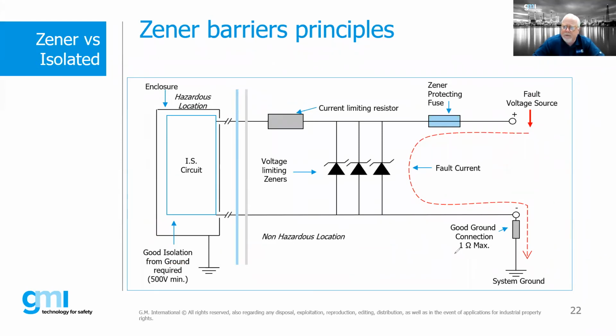But notice this: 1 ohm max, good ground connection. This requirement is pretty much worldwide, 1 ohm max resistance of our system ground. Notice that this ground here is considered our IS earth, or a clean earth. We don't want to tie this earth in with all of our other tied-in earth points within our facility, because we could suddenly get all kinds of noise coming right back up into our system and defeat the whole purpose.